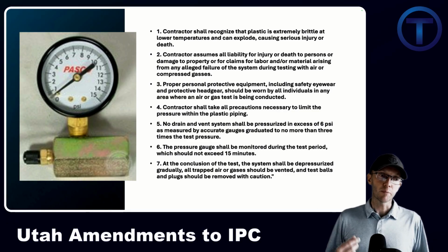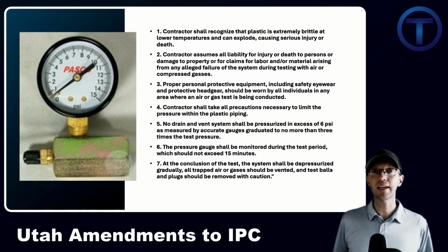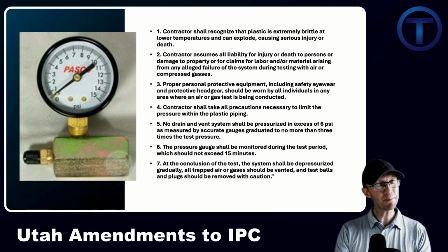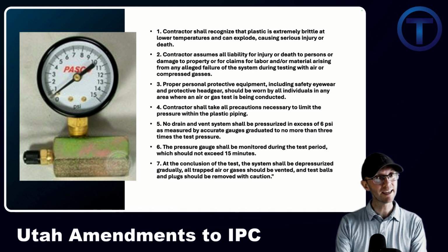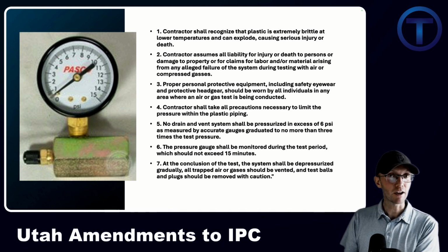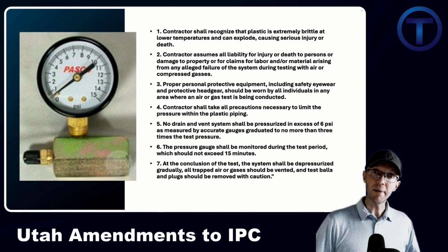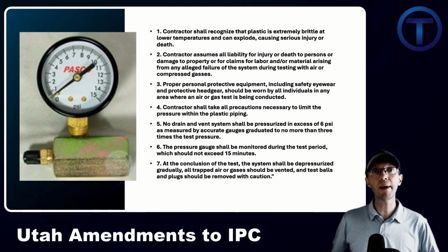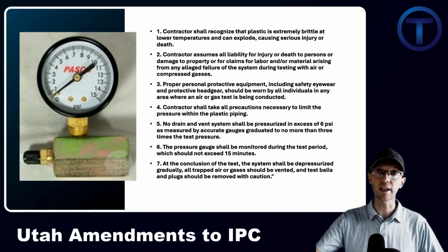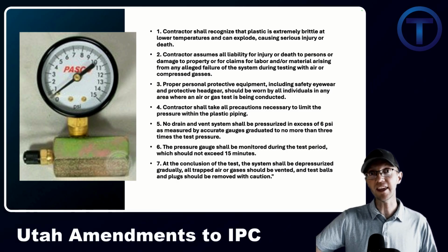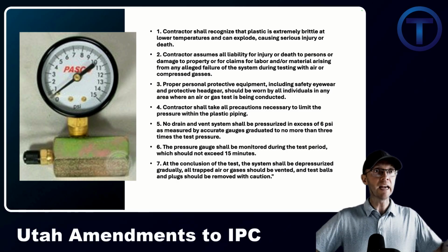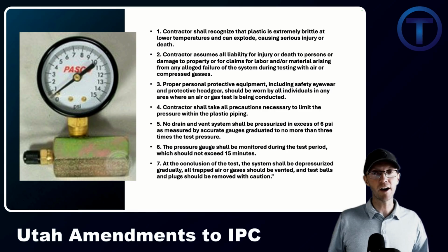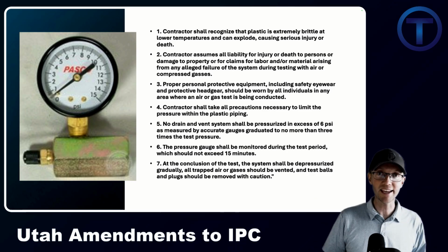Number 6, pressure gauge shall be monitored during the test period, which should not exceed 15 minutes. This is a little bit difficult. You heard that, right? Code says you have to have the test on for at least 15 minutes. Amendments say you should only have it on for 15 minutes. This is a little problematic when I call in for an inspection and I'm told by the code official, we'll be there sometime today. I don't know when, but sometime today.